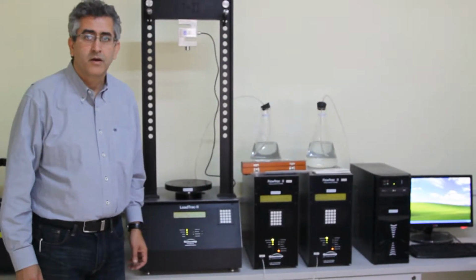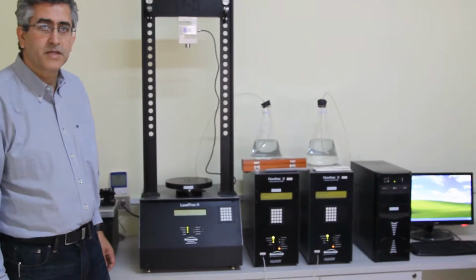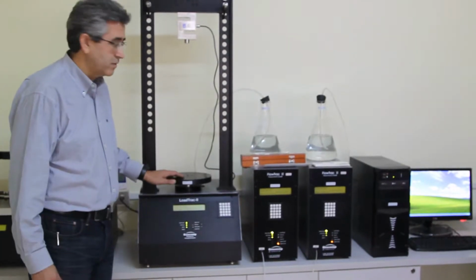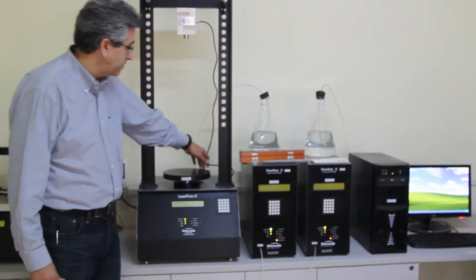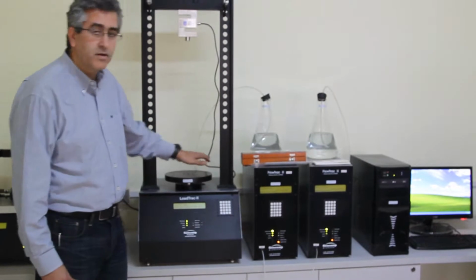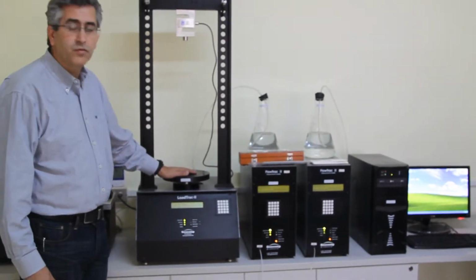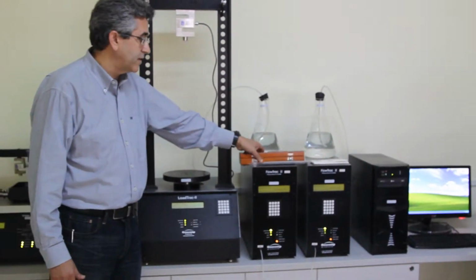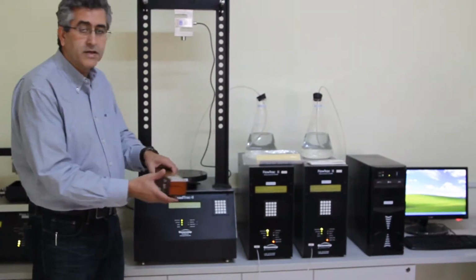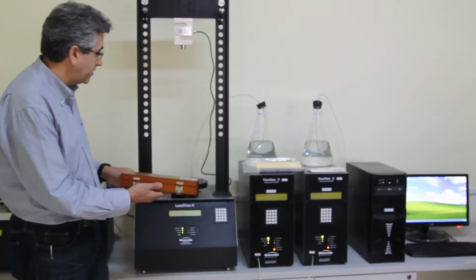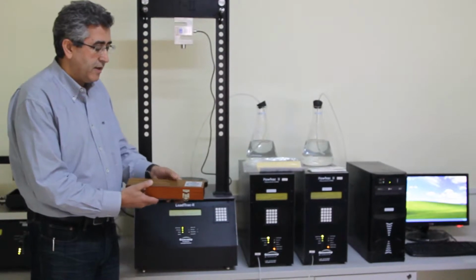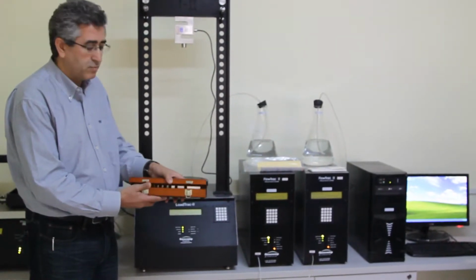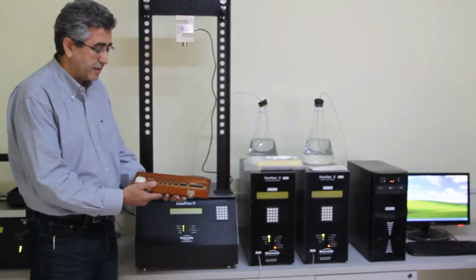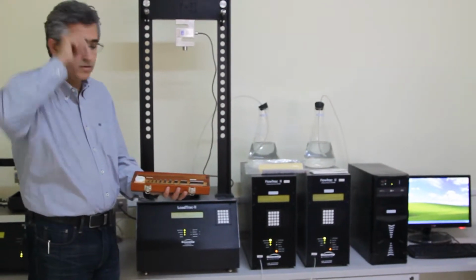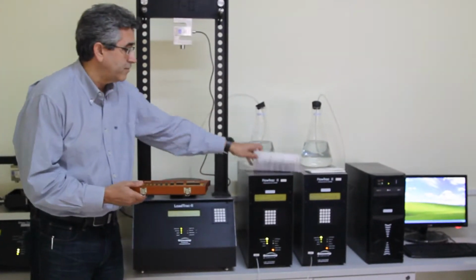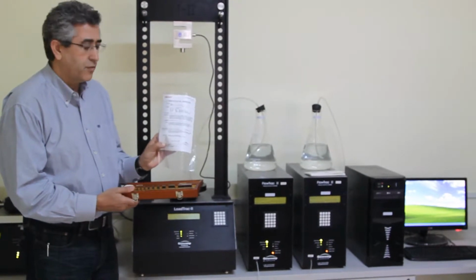Hi, today we are going to do the calibration of the displacement sensor for the LoadTrac 2 unit. The displacement sensor is underneath the platen here. We are going to need a calibration device or reference that is traceable. In this case, today we are going to be using a set of gauge blocks, and those are calibrated and they are traceable. They come with their own calibration certificate. This is valid for 1 year.